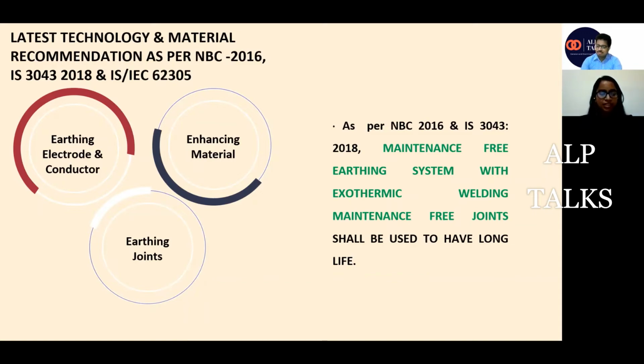Now the latest thing which is recommended by the standards is the use of solid rods, not plate earthing or hollow pipes. Because with solid rods, first of all, manufacturing defects are eliminated from the earthing system. Secondly, with solid rods, we can use material like MS or copper steel rods. The best material to use is obviously copper, but it is too costly. So to reduce the cost and to give the proper conductivity and features of copper, this copper bonded steel material has been innovated.